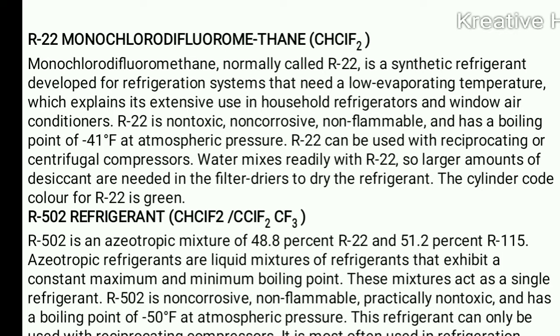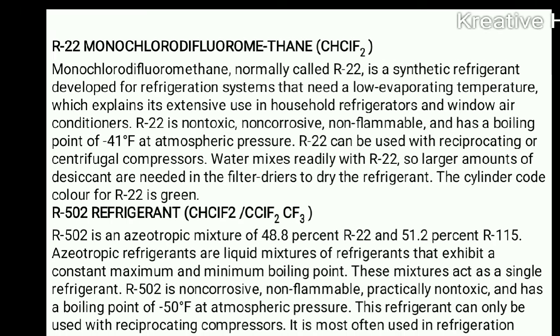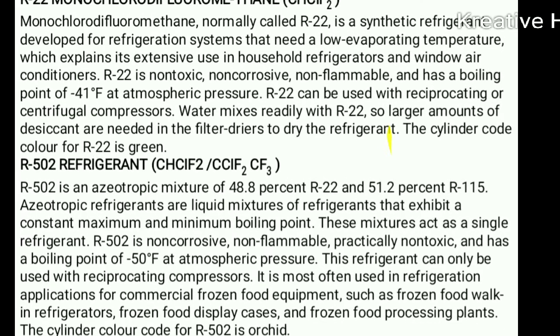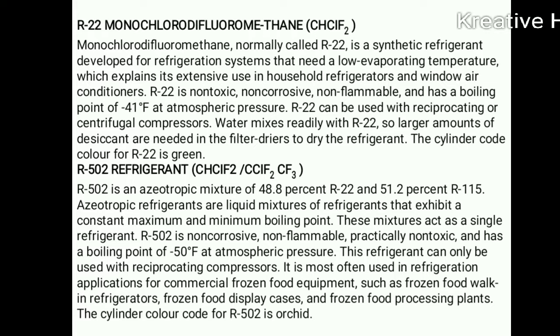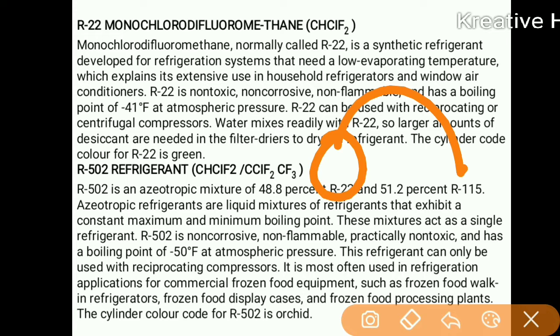R502 is a very important azeotropic refrigerant mixture. It consists of 48% R22 and 51% R115 mixed together to make R502. The azeotropic refrigerant is a liquid mixture of refrigerants that contains a maximum or minimum boiling point, behaving like a single substance. R502 is non-corrosive, non-flammable, and practically non-toxic, with a boiling point of minus 50 degrees Fahrenheit.